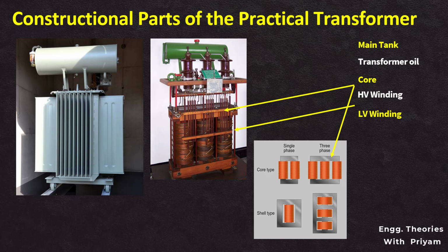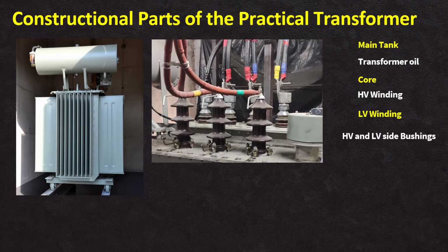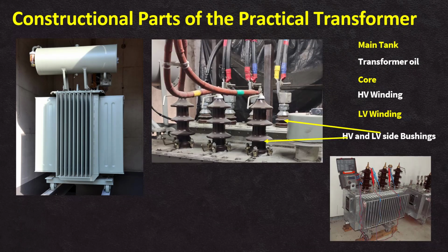Next component that we want to talk about is HV and LV bushings. In a transformer, bushings are strategically positioned on the transformer tank to facilitate the crucial task of electrical insulation and mechanical support. They serve as essential components providing both electrical insulation and mechanical support to the conductors passing through the transformer tank. These insulating structures play a pivotal role in preventing the electrical discharges and ensuring that the high voltage within the transformer remains contained. By offering support to the conductors, bushings help maintain their position and alignment, contributing to the structural integrity of the transformer. There are different types of bushings, including oil-filled and dry-type variants, each tailored to specific operational requirements.